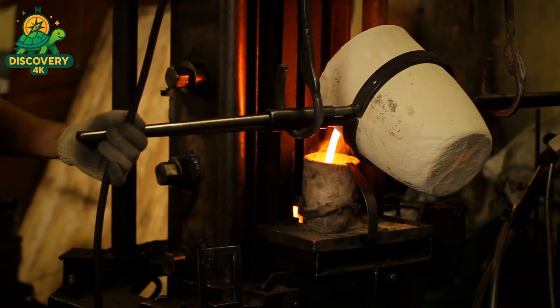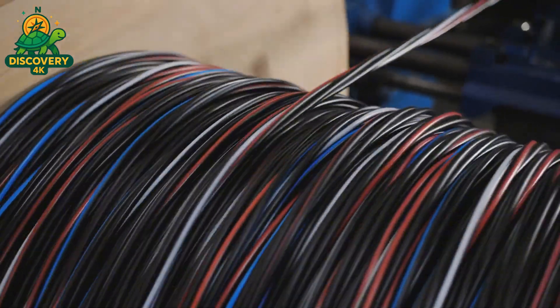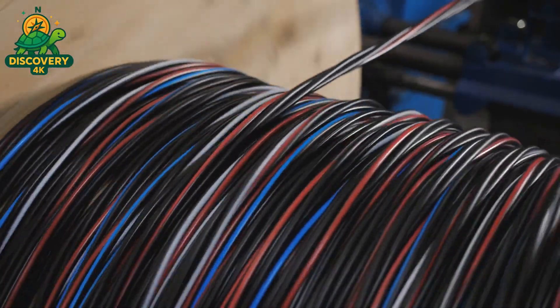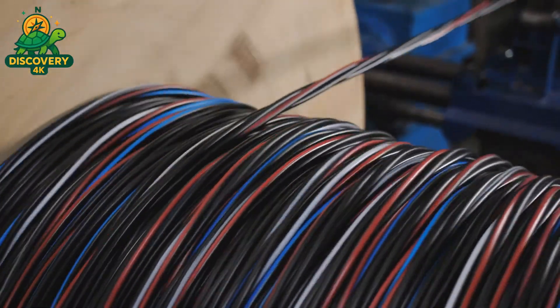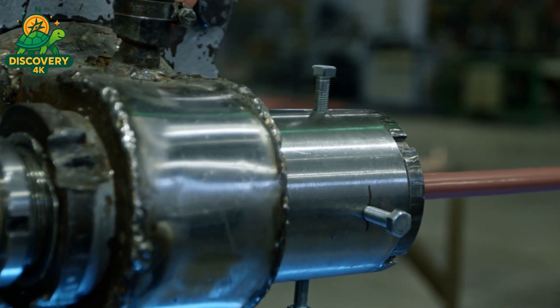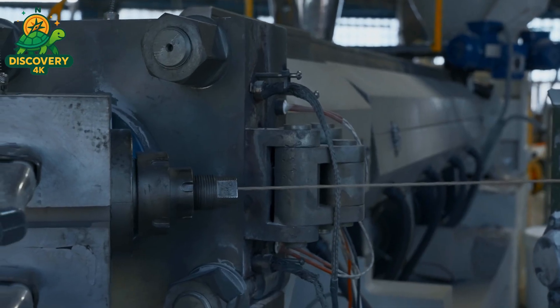What emerges is more than just wire with a coat — it's a functionally advanced material tailored to resist heat, water, voltage surges, UV radiation, chemicals, and oils. Different applications demand different insulations: in homes, flexible PVC, safe and affordable; in high-voltage lines, cross-linked polyethylene (XLPE), heat-tolerant and tough; in hospitals or aircraft, low-smoke halogen-free compounds to protect lives in case of fire. Laser gauges along the line measure insulation thickness 1,000 times per second. If it's even a hair too thin, the cable is stopped, flagged, and reprocessed — because when carrying thousands of volts through a concrete wall or data through a server farm, there's no room for error.